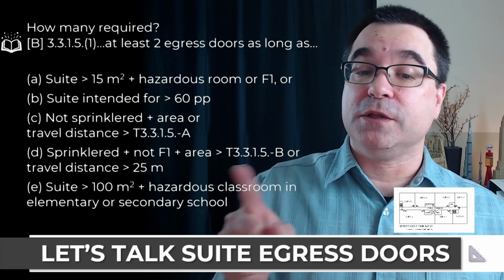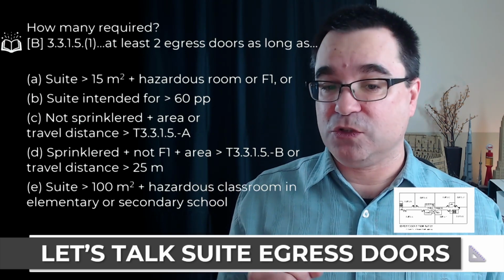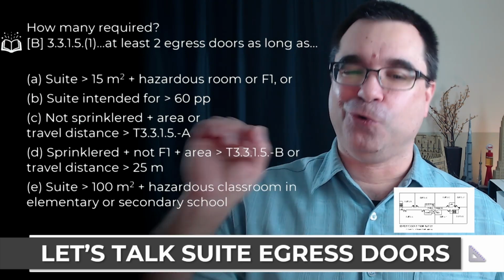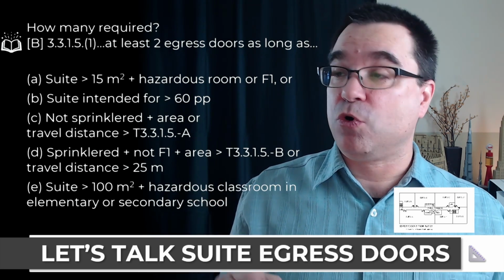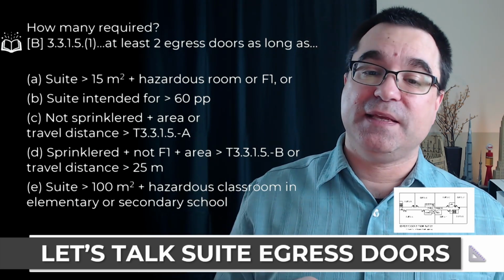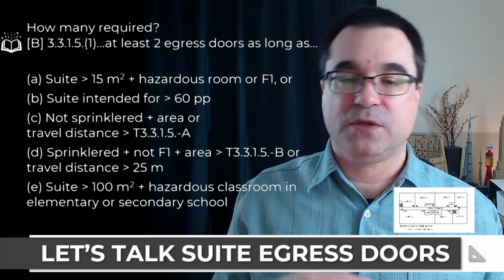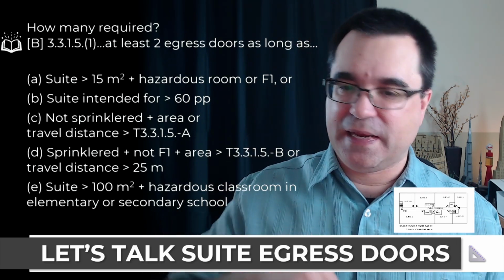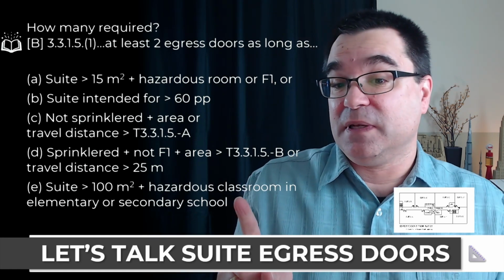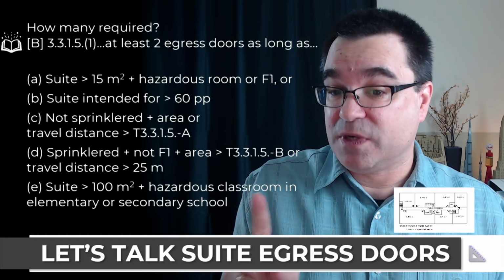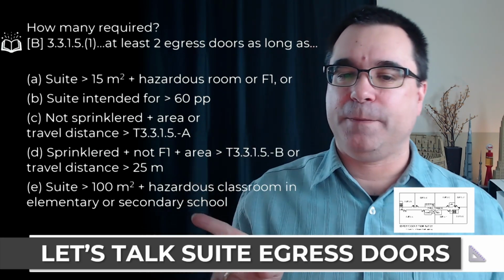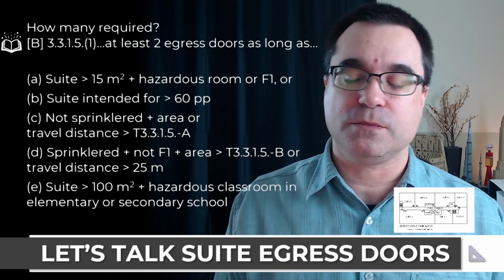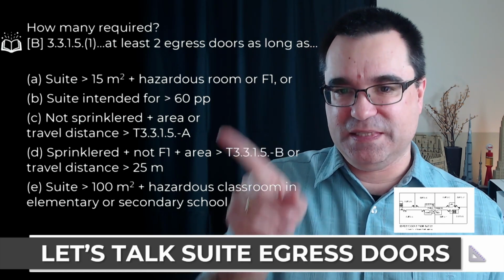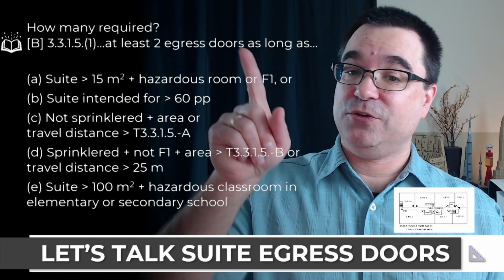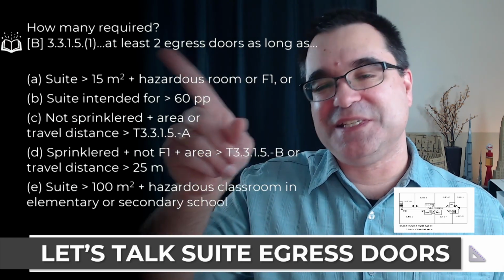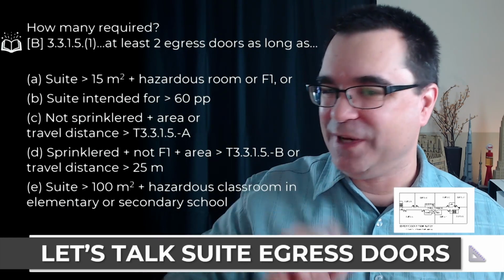3.3.1.5b, or the travel distance in that space is more than 25 meters, or lastly, if that suite is more than 100 meters squared and it contains either a hazardous classroom in an elementary or secondary school. So think even like a shop space, right? Some shop spaces in elementary or secondary schools can be hazardous classrooms. If any one of these is true, then you need at least 2 egress doors, or as this sentence says, more than 1 egress door.